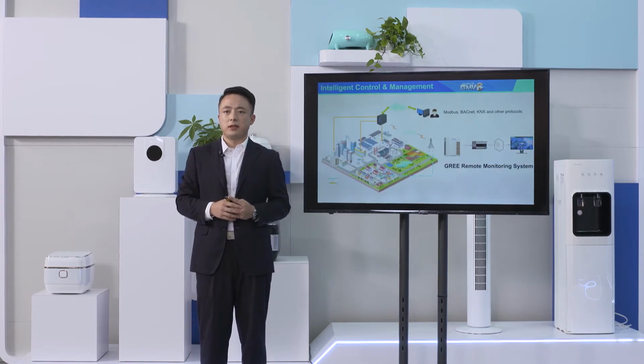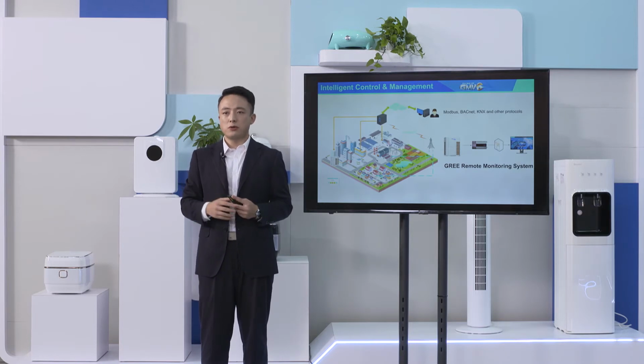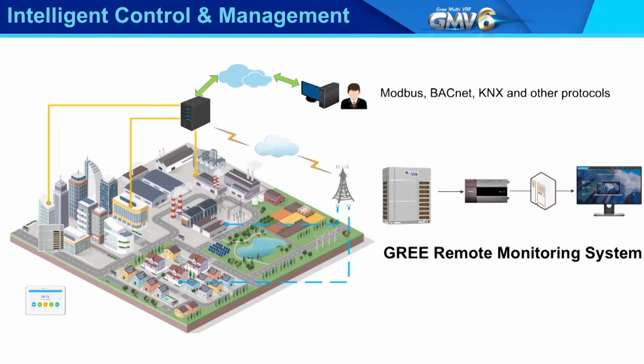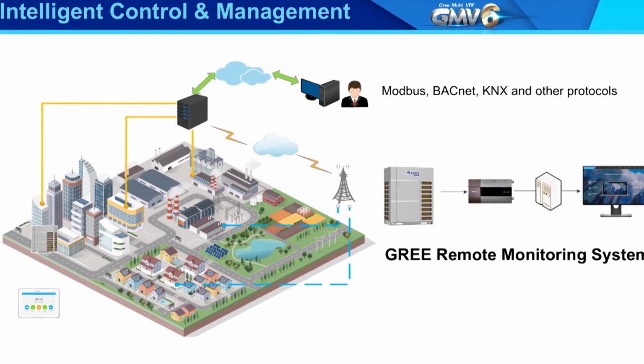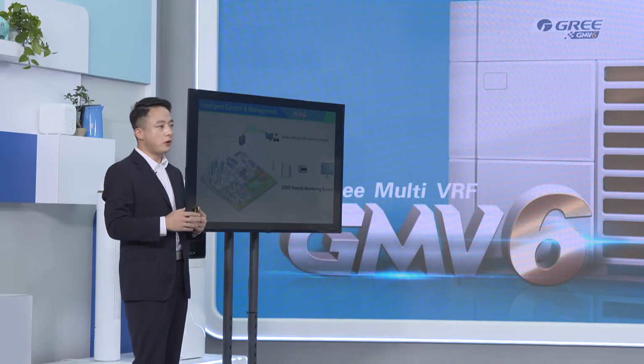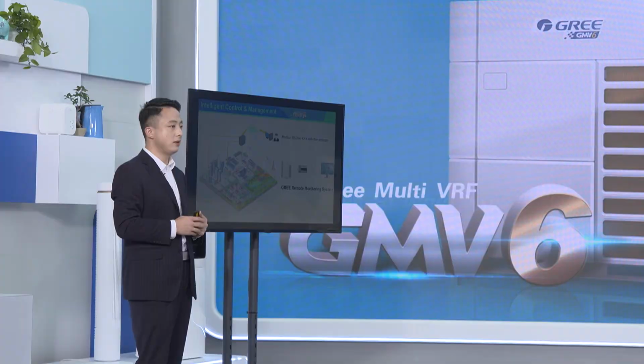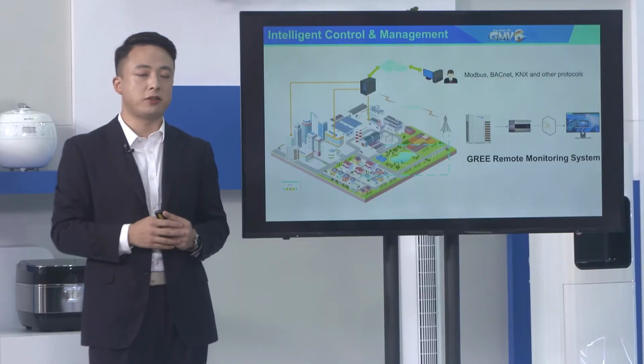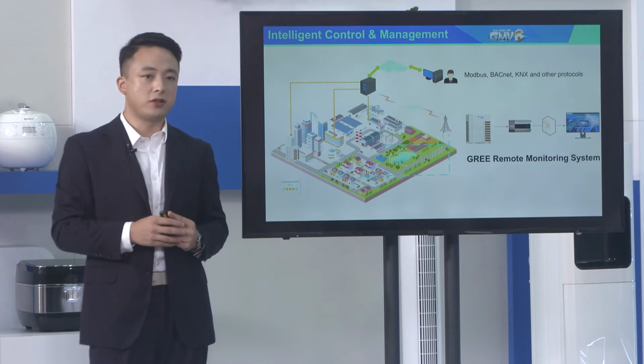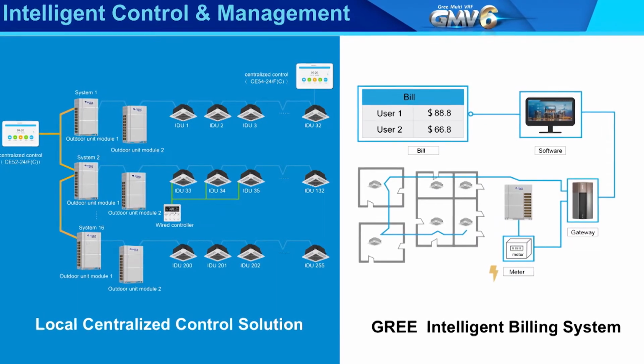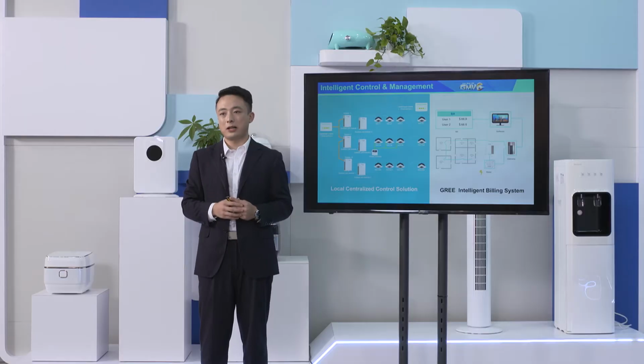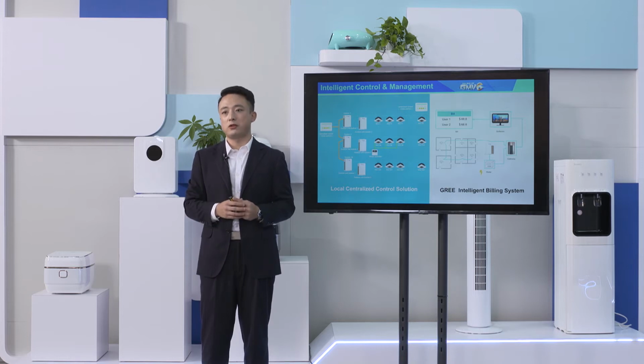For large public buildings, centralized control is convenient for management, which is a current mainstream demand. Gree centralized and intelligent control system for GMV6 supports Modbus, BACnet, KNX, and other protocols. We also provide wired solutions to solve the monitoring of a large number of centralized air conditioning equipment and wireless solutions for fast and flexible monitoring, suitable for difficult wiring situations and for distributed monitoring. Gree intelligent billing system can solve the problems of multi-VRF power consumption statistics and user electricity bill distribution, and provide accurate and reasonable billing basis for property management.